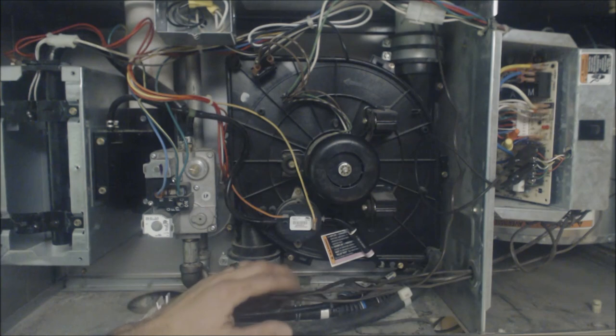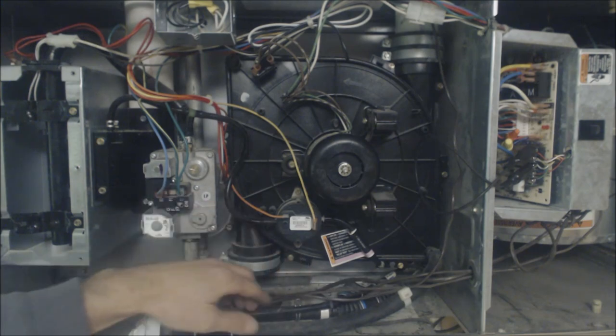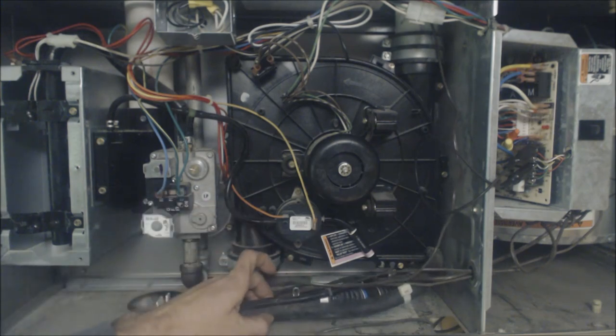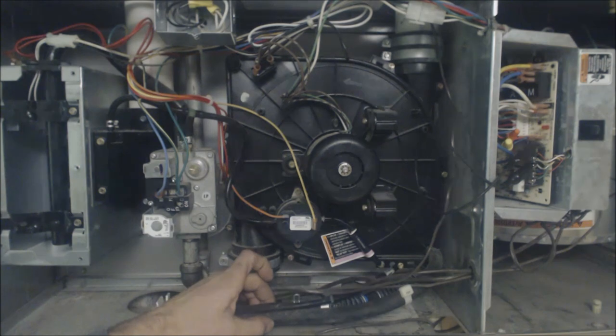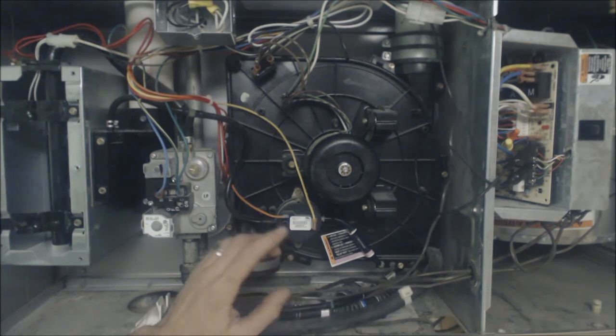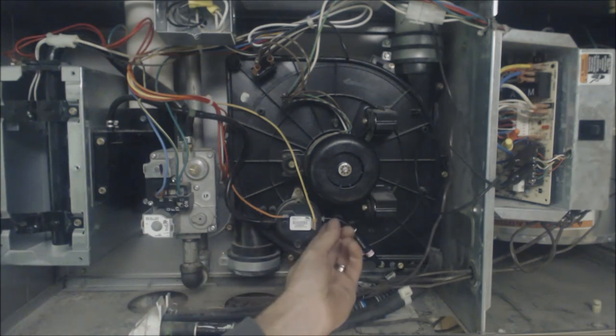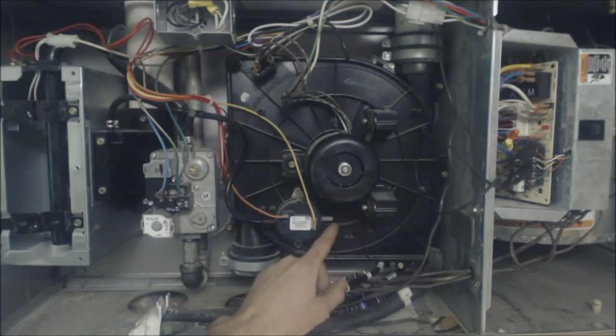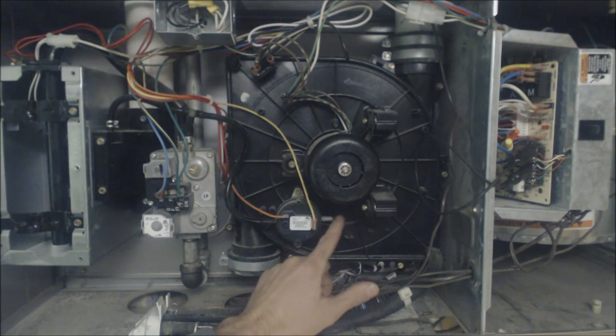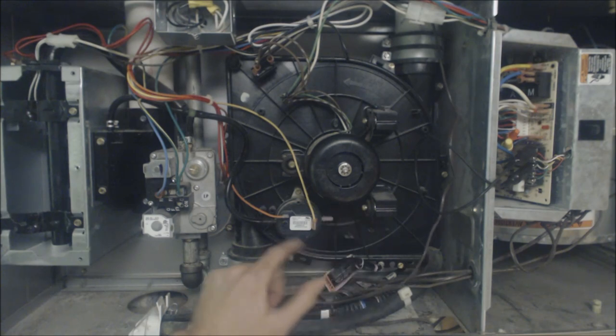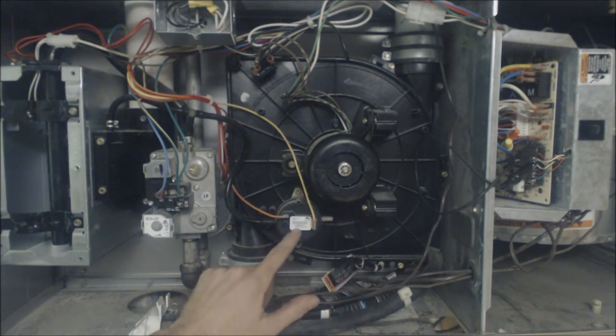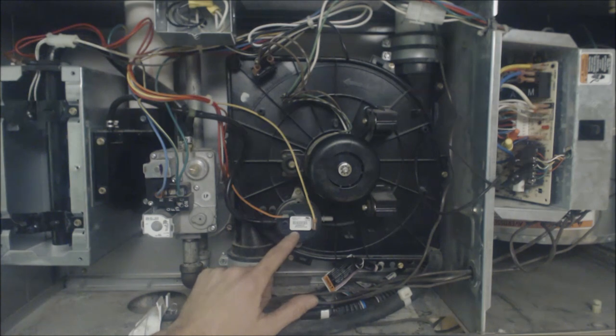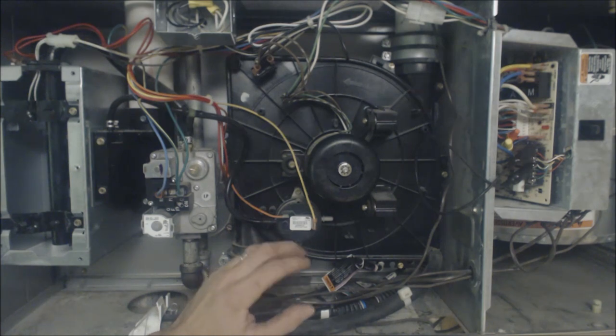And once again, you know, if you want to blow these out you want to make sure that this is disconnected, alright. Make sure that you're not getting any pressure into this. I would not advise sucking on these or anything like that. You're going to put too much pressure, negative pressure on the pressure switch and possibly mess up the inside.